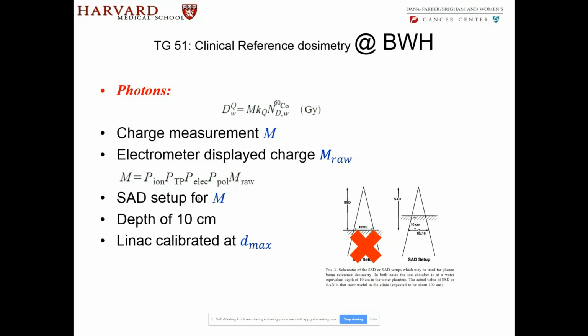Linac is calibrated at Dmax. What does that mean? That means that at the depth where you get maximum dose, one monitor unit will correspond to 1 centigray within 1%. And we'll come back to that again. That's at a depth of, for 6 MV, 1.5 cm, because that's where the maximum dose from 6 MV is delivered. Clinical TMR curves are used. Again, I'll come to that on the next slide.